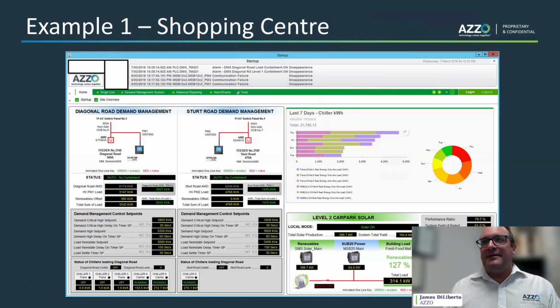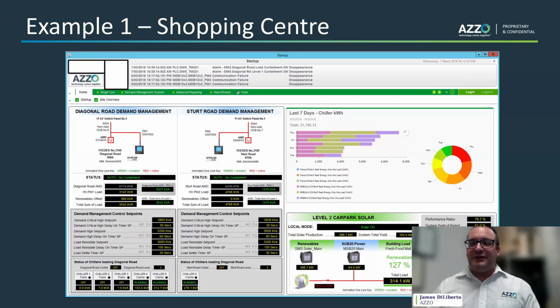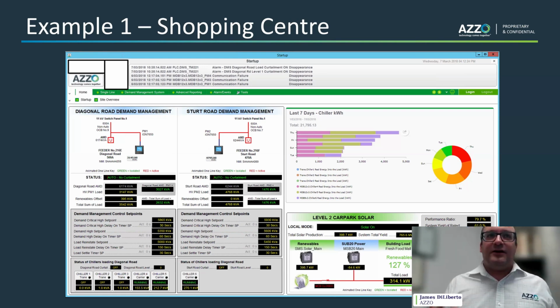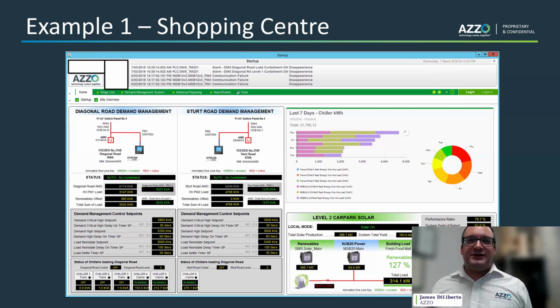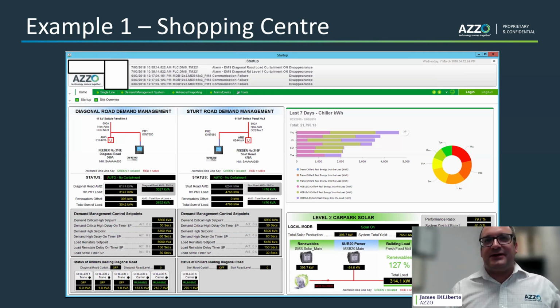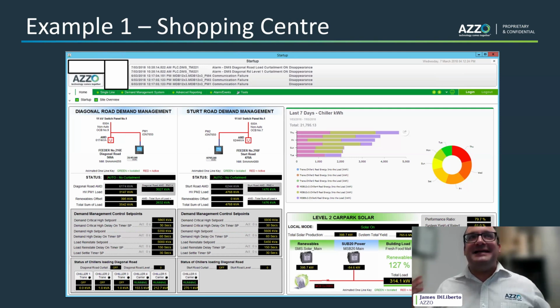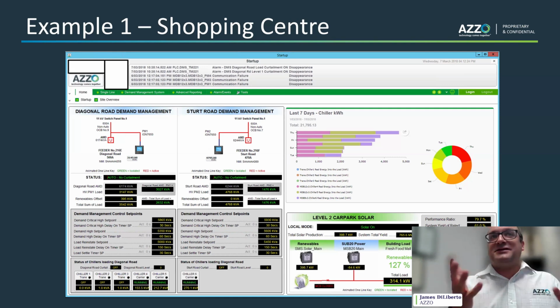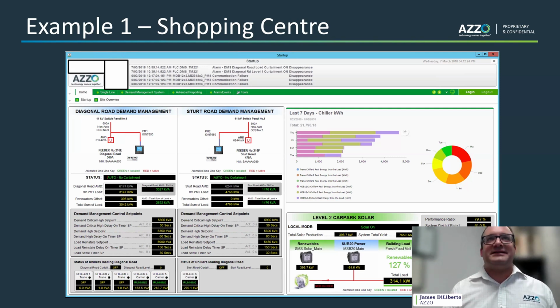First, a shopping center. They were facing a large transformer upgrade to put in a new wing of the shopping center. Instead, they installed a large amount of car park solar and implemented a demand management system, taking advantage of the building envelope and making sure the loading and unloading of the chiller management system on site was done in a way that avoided upgrading the transformer. For those rare times, as the previous presenter showed on the duration curve, you don't actually need that much capacity. If we can manage it in a shorter, faster amount of time, we can avoid it. Maybe you or your customer is a shopping center - great example to avoid a large transformer upgrade.